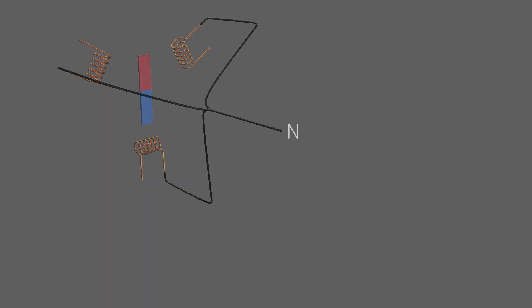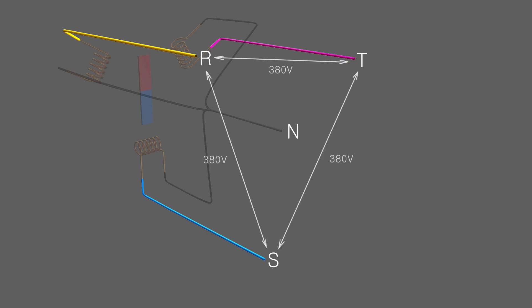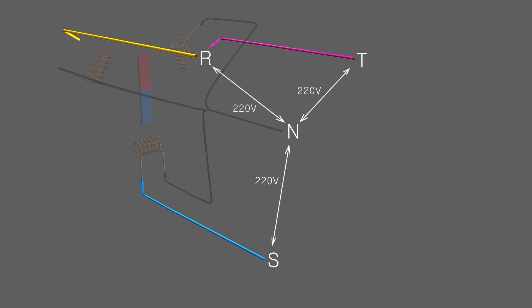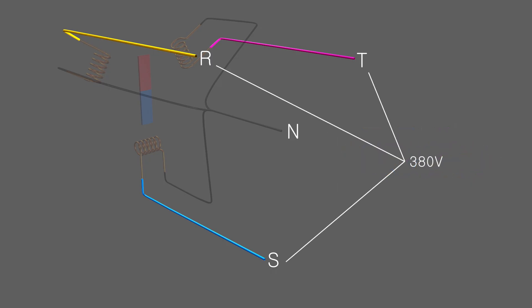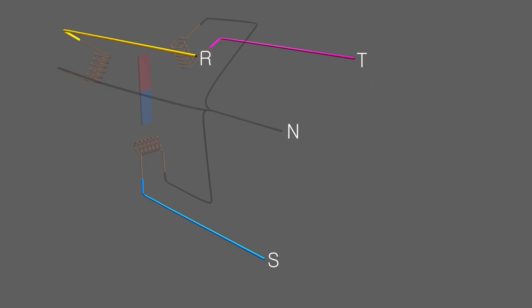When we connect the other end of the coil with a wire to tie them together, this neutral wire does not show any phase. Meanwhile, R, T, and S phases have a 380-volt difference from one another. Between R, T, S, and the neutral wire, there is a voltage difference of 220 volts. The electric currents produced at power plants flow into our homes and factories in the form of three phases. 380 volts generated by three wires is mainly used in industrial settings for electric motors, while 220 volts generated by connecting an electric wire with the neutral wire is used at home.